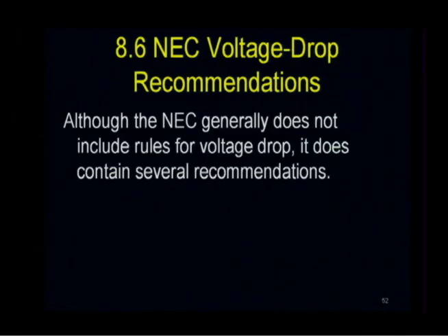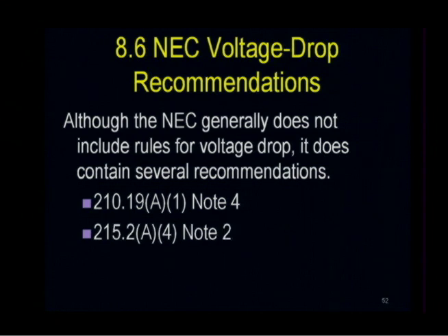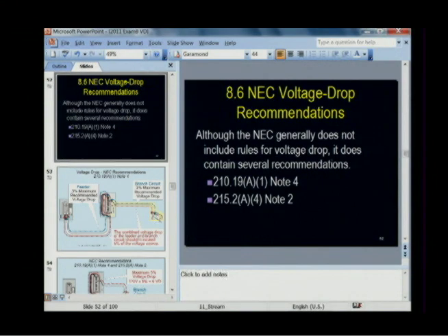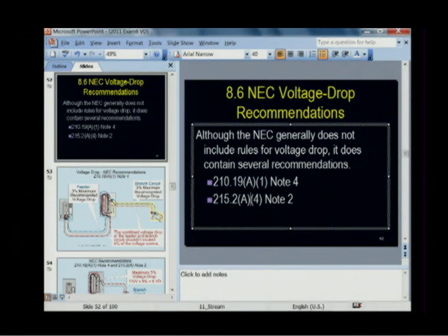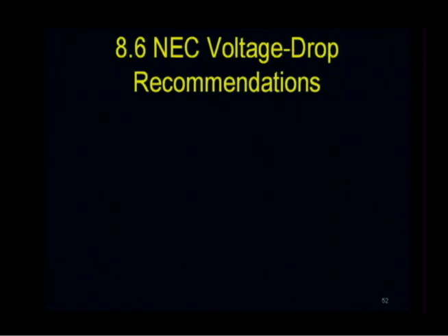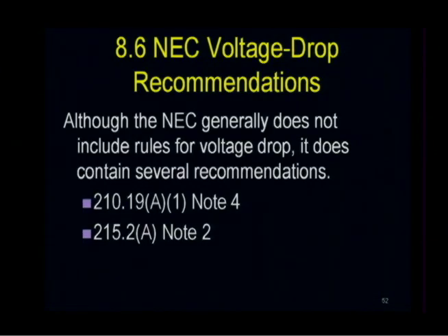The NEC recommendation. Although the NEC generally does not include rules for voltage drop, it does contain several recommendations. 210.19(A)(1), Note 4, we talked about that. 215.2(A), and I guess if I had to do this again, I'm going to change this, Steve, to 215.2(A), and that would be simply Note 2, right? Yeah. Because it's not a note to number 4, it was just a note to 215.2(A), Note 2. We need to make sure that textbook has that in there.